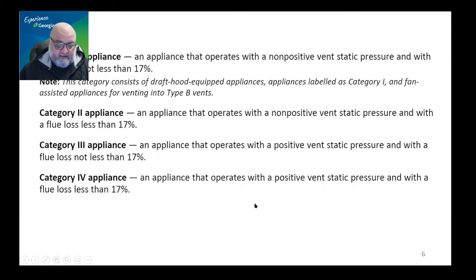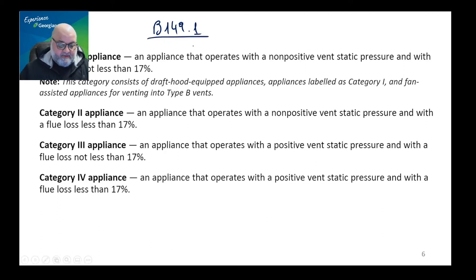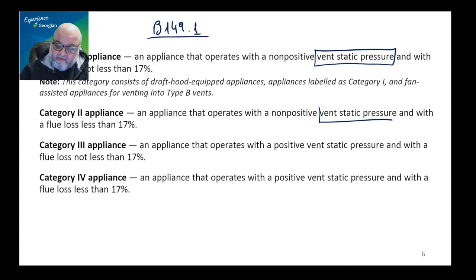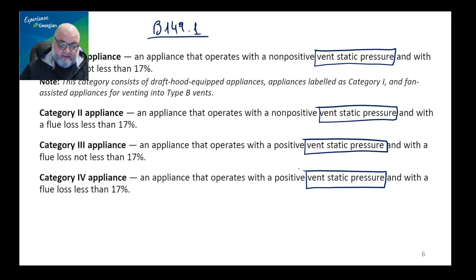This is in your codebook B149.1 in the definitions, and it mentions that there are four categories: one, two, three, and four. If you look closely at the definitions, an appliance that operates with a non-positive vent static pressure — the vent static pressure is one criteria mentioned in all four definitions. And the other criteria we have is flue loss, which is also mentioned in all four categories.